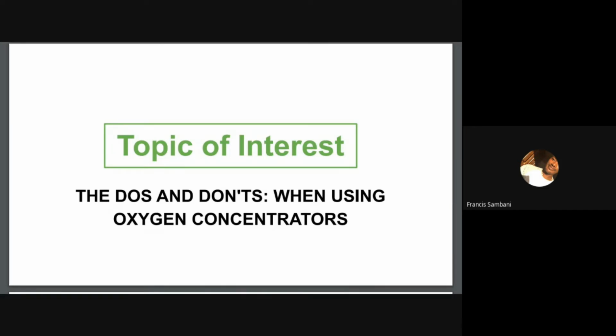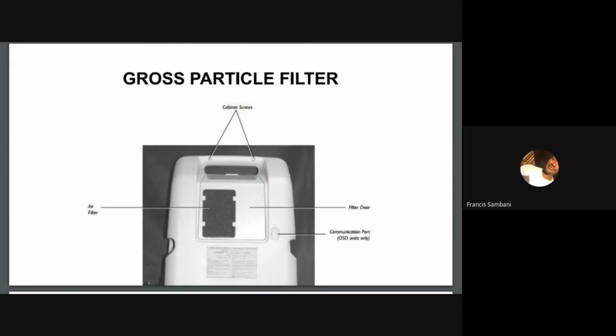Prior to using your oxygen concentrator, you should make sure that it has all filters in place and that they are clean. That being said, you are not supposed to use an oxygen concentrator if the gross particle filter is wet, like it is damp, something like that. The air filter should be monitored more closely in environments with abnormal amounts of dust and lint. So I said that you're not supposed to use it without the gross particle filter. If you don't have a gross particle filter, you're not supposed to use a foam mattress as a replacement for the gross particle filter. The best solution is for you to have a replacement gross particle filter.